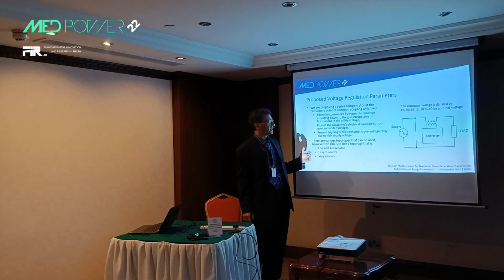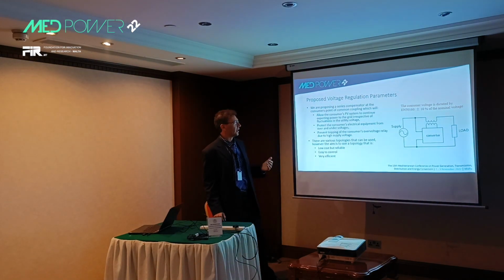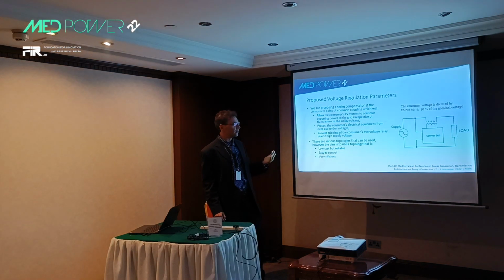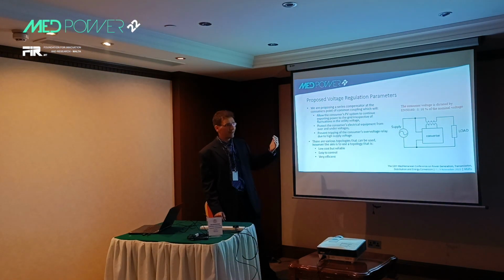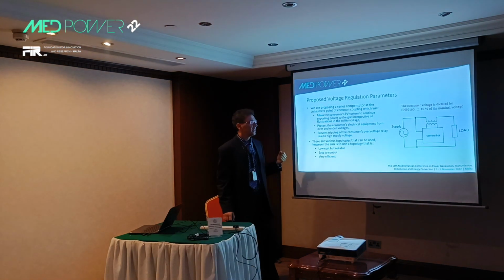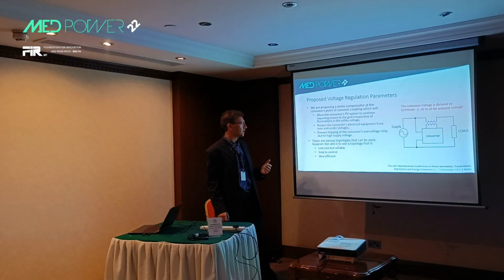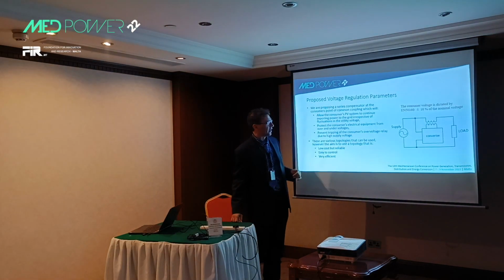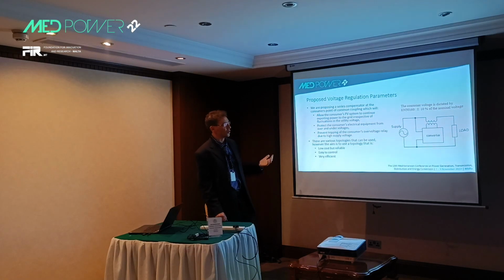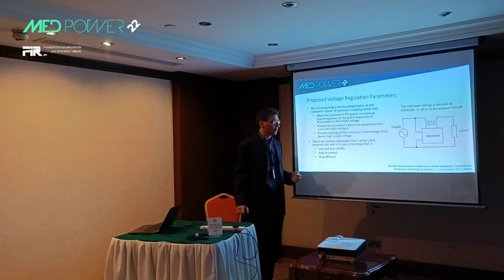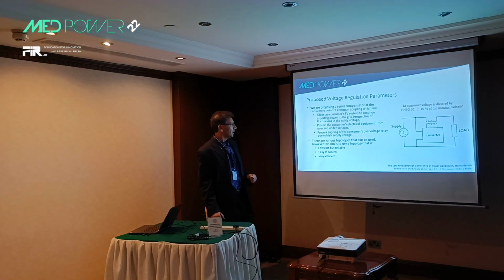Also, this type of circuit will be able to protect equipment from over and under voltages because it's an active voltage regulator. It's fast enough to correct the voltage, and it will also prevent the tripping of the consumer's overvoltage relay, which is something which recently has been introduced into the Maltese electrical grid.